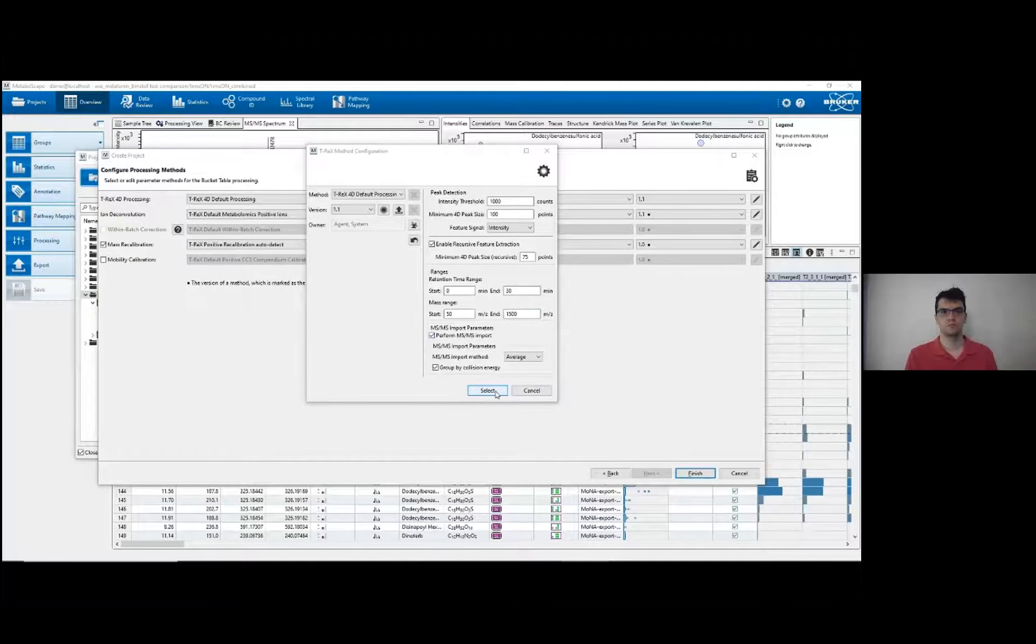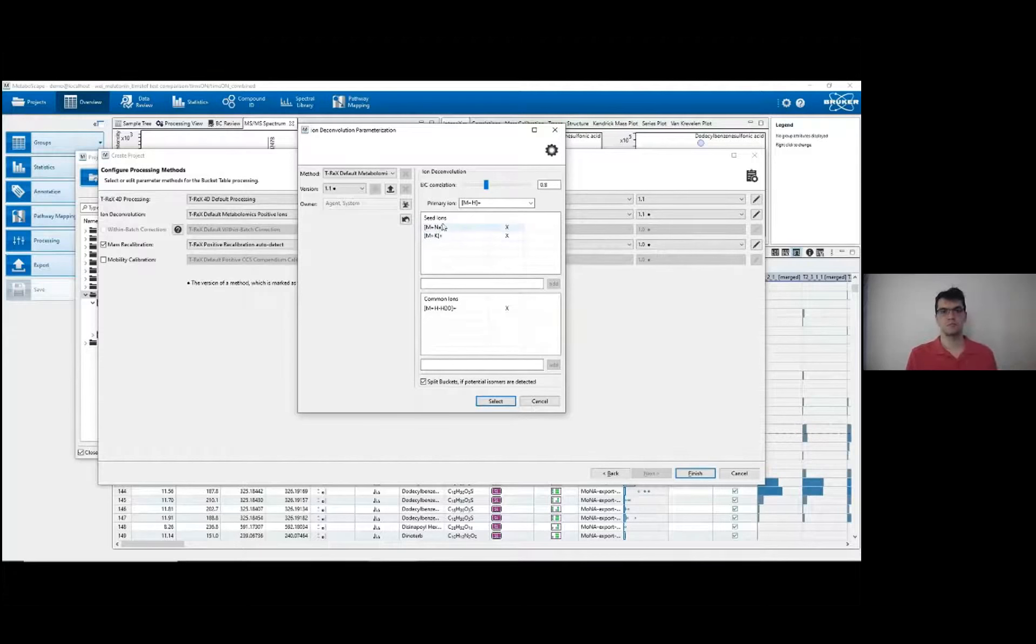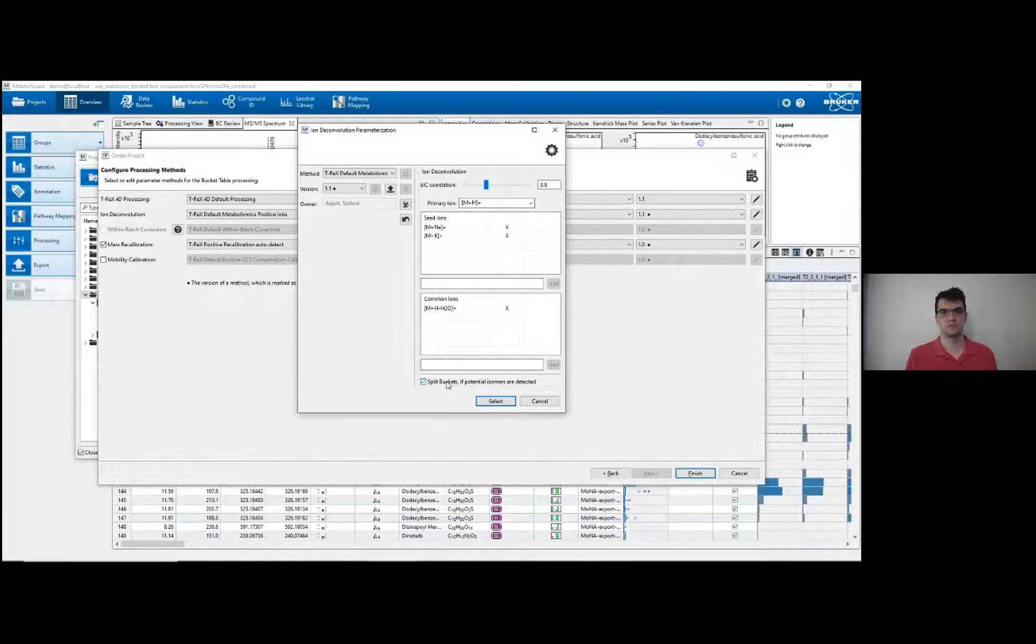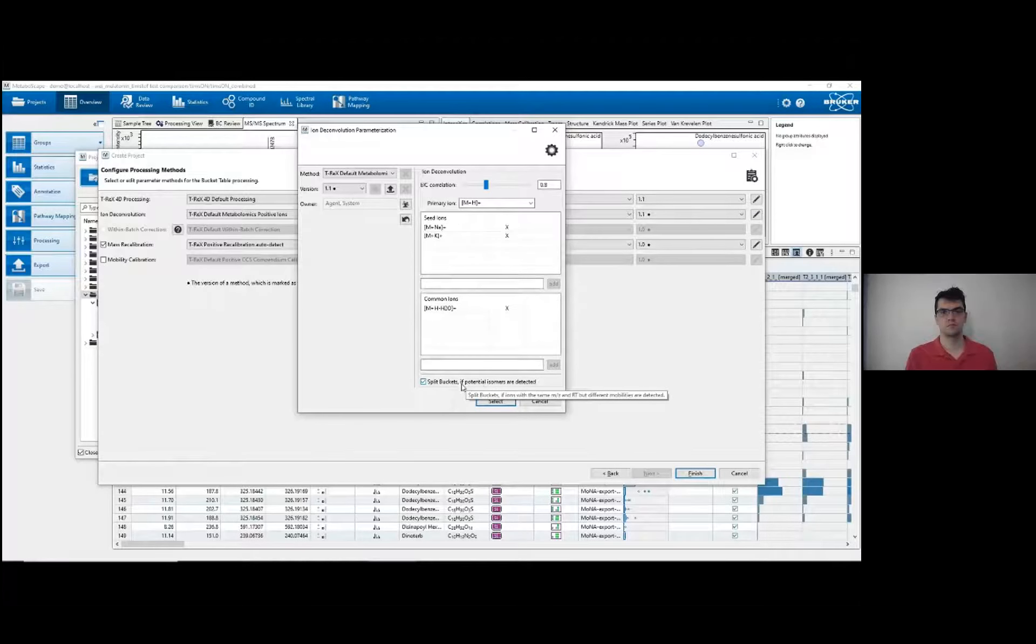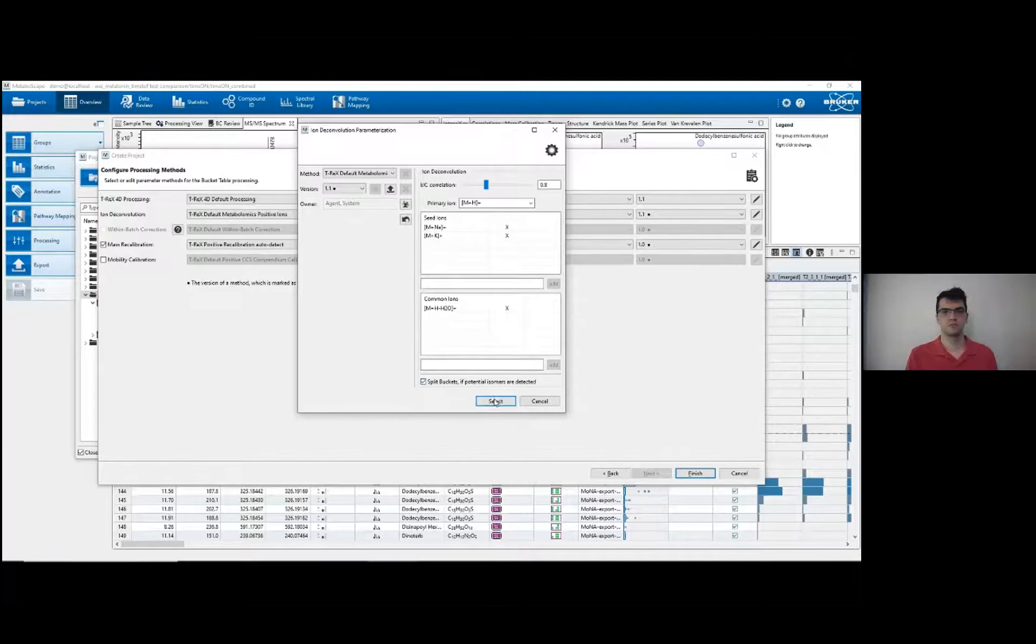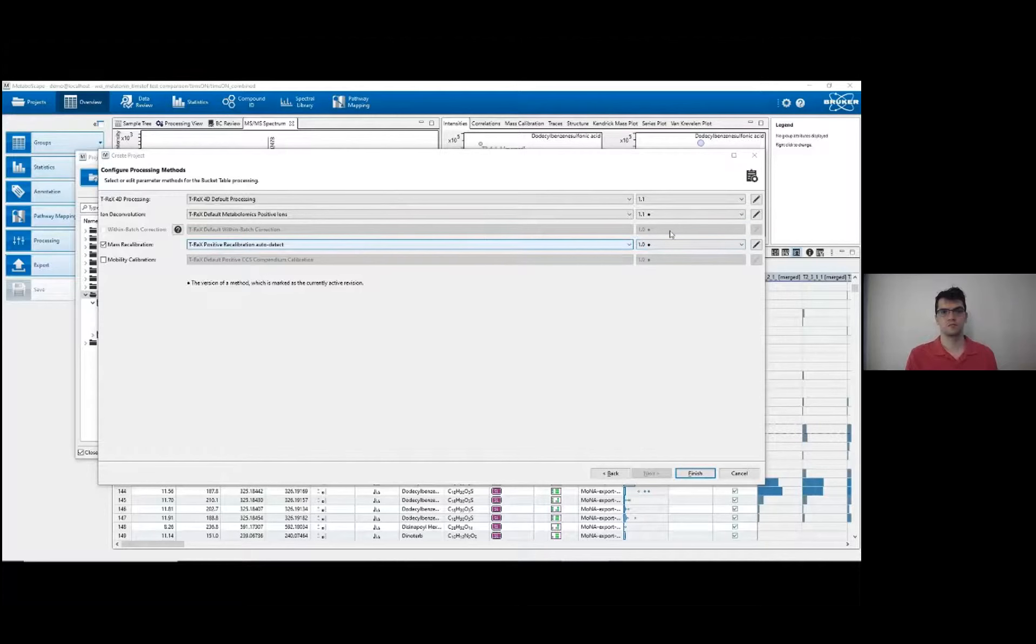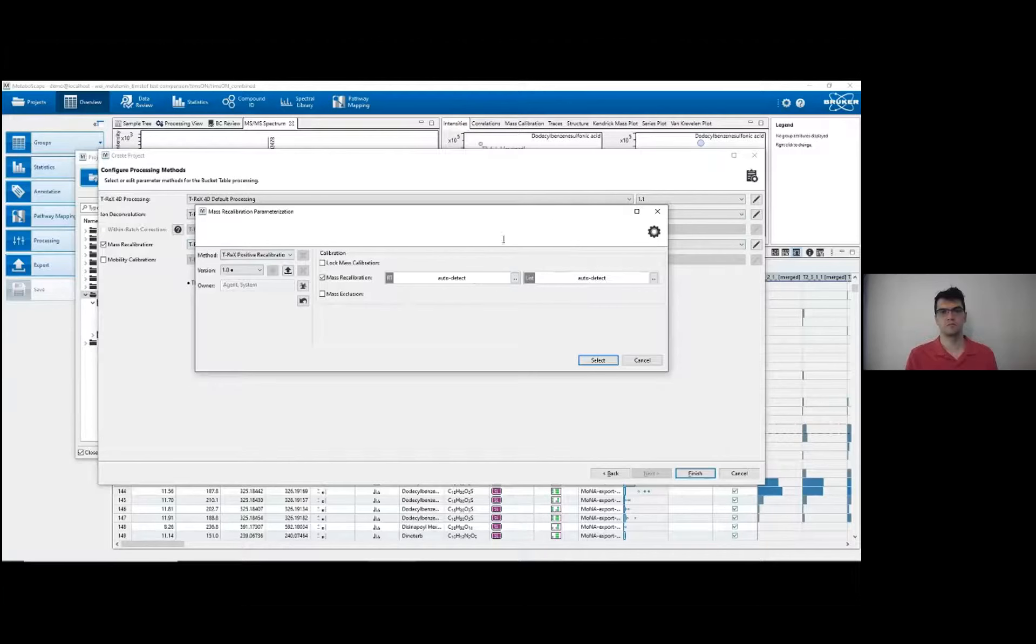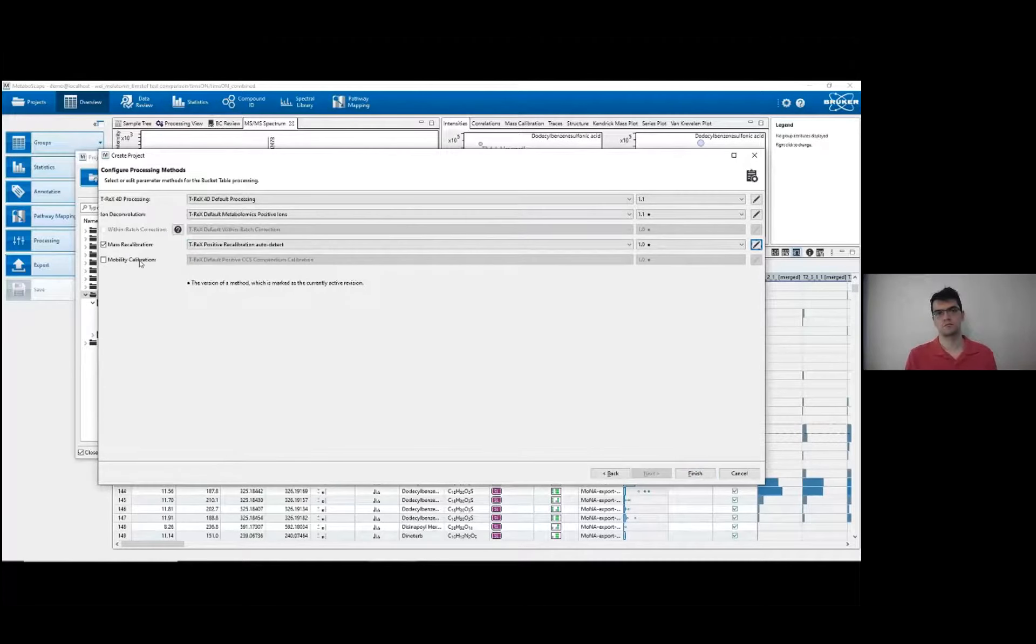Next, we'll move on to some of the ion deconvolution settings. These algorithms help identify different ion adducts. Generally, I don't need to change these settings much since in positive mode these are the most common ions. The split bucket setting is potentially quite useful. If you suspect you have different isomers that can be separated, leaving this on can help you identify those, especially thanks to the ion mobility system, if you have that on. The mass recalibration settings generally don't need to be changed much. These are useful when you have the switching valve running that injects calibrant before each sample run. These don't really need to be changed since it auto detects sodium formate or tune mix within each sample, so I just leave that on.